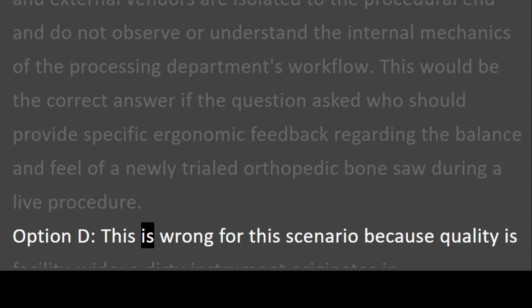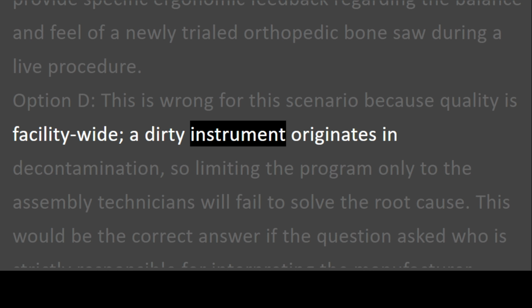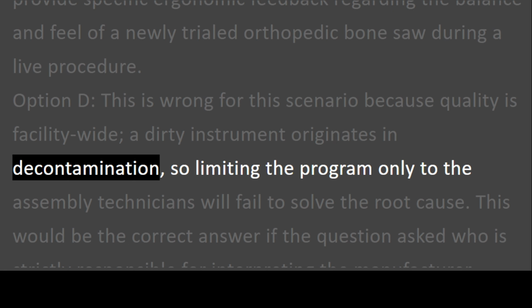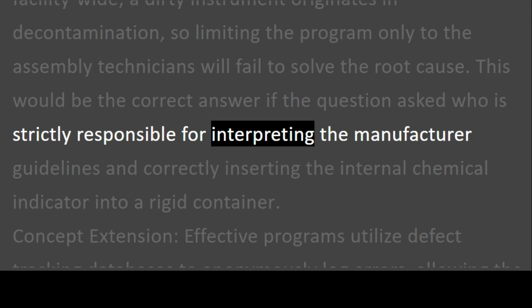Option D. This is wrong for this scenario because quality is facility-wide. A dirty instrument originates in decontamination, so limiting the program only to the assembly technicians will fail to solve the root cause. This would be the correct answer if the question asked who is strictly responsible for interpreting the manufacturer guidelines and correctly inserting the internal chemical indicator into a rigid container.